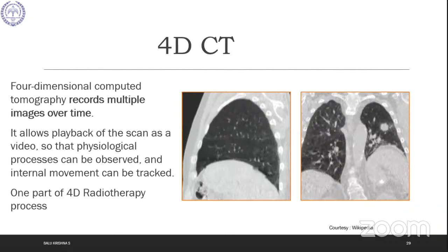So a 4D CT comes with respiratory monitoring equipment. The respiratory monitoring equipment that we employ is the Real-time Position Management system from Varian. Most of you have seen it. It comes with an infrared box, a small box, which is kept just below the xiphoid process of the patient, which is standardized. We keep it and then we actually mark it and tattoo it so that it can be reproducibly positioned for treatment delivery also. And there is a fixed camera in the treatment room as well as the imaging room, in the same position, which will detect the transducers through infrared.